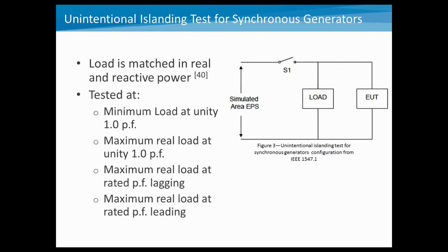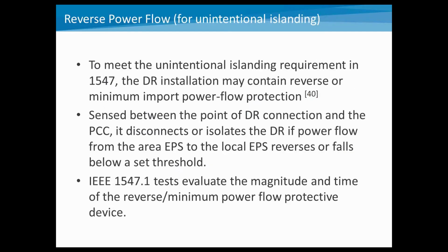As we look at a couple other tests inside of 1547.1, there's one for synchronous generators. Again, the key here is to match real and reactive power and then get zero current flow across switch S1, and open that up. For synchronous generators, this is done at things like minimum load at unity power factor, maximum load at unity power factor, real load at rated power factor, leading and lagging, so a variety of conditions. And then there's also a test in there for understanding reverse power flow. So, for example, if you have reverse power flow protection in the case of relays, you're able to set up and test and evaluate those.